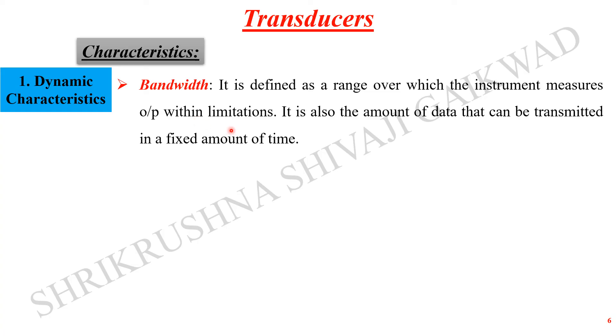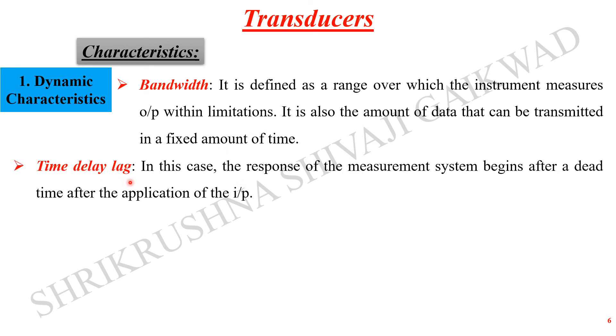Bandwidth is the range over which the instrument measures the output within given limitations. It is also the amount of data that can be transmitted in a fixed amount of time. Time delay or lag refers to the condition where the response of the measurement system begins after a dead time following the application of the input — that is, the system does not respond to changes happening in the input during this dead time.